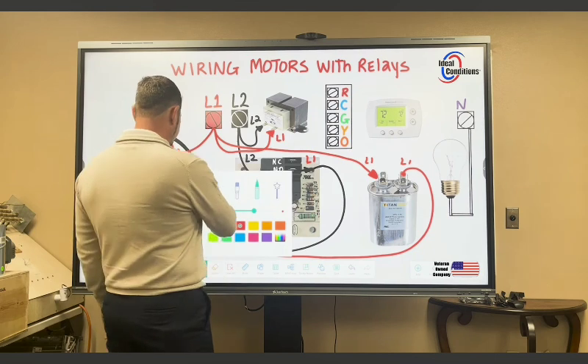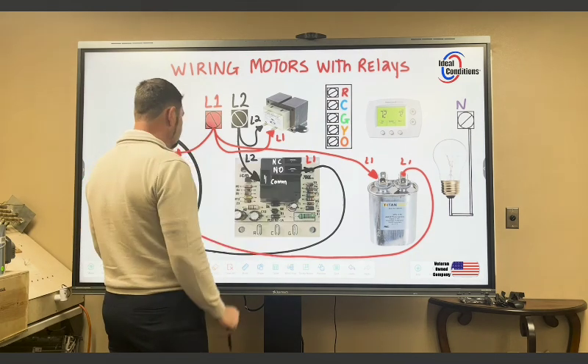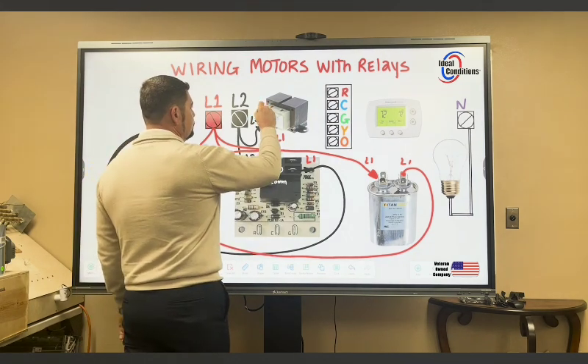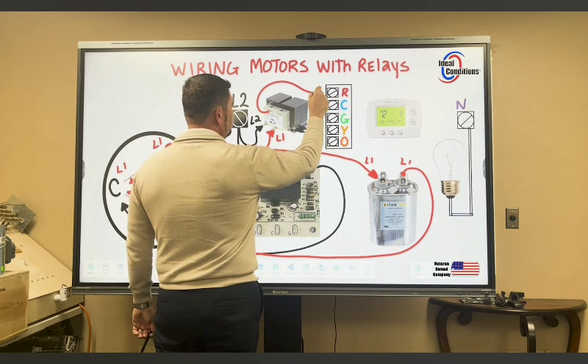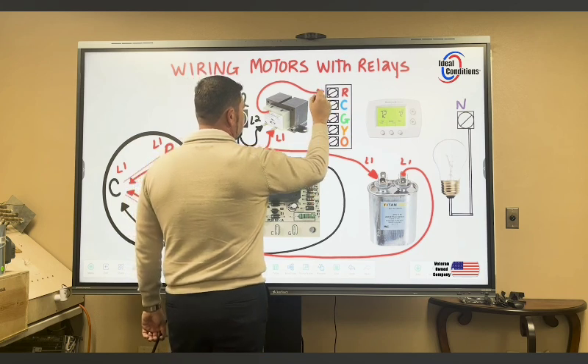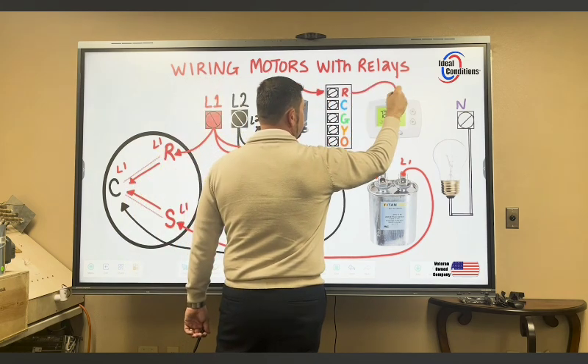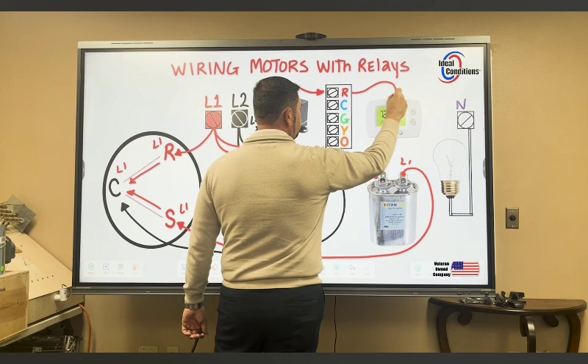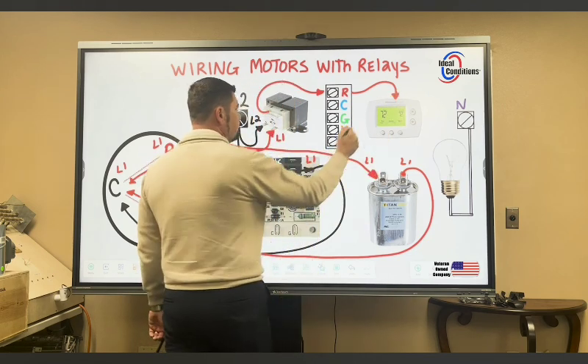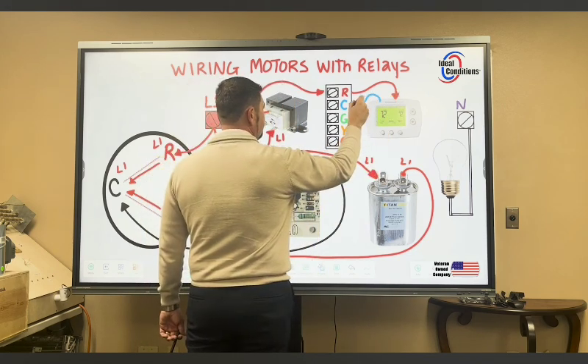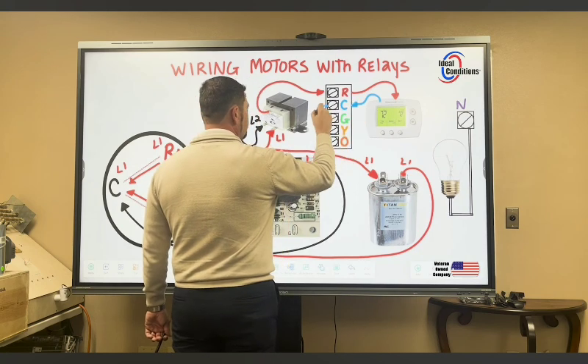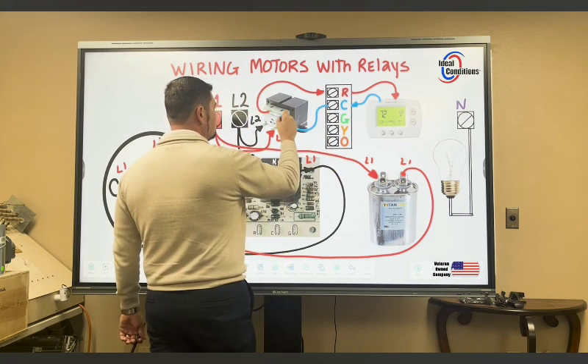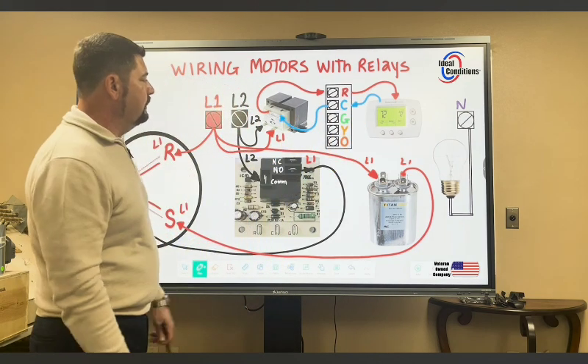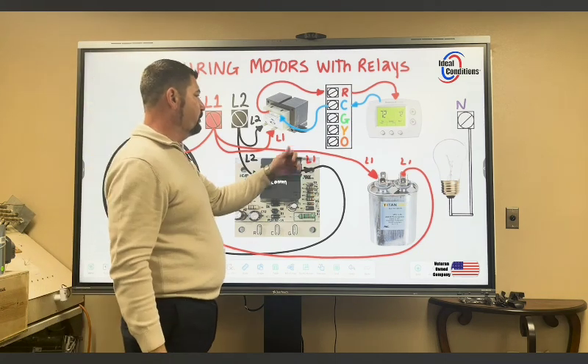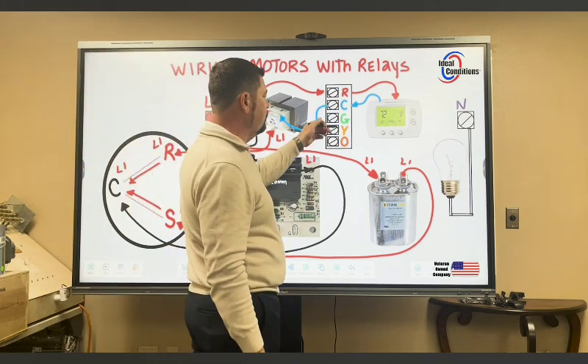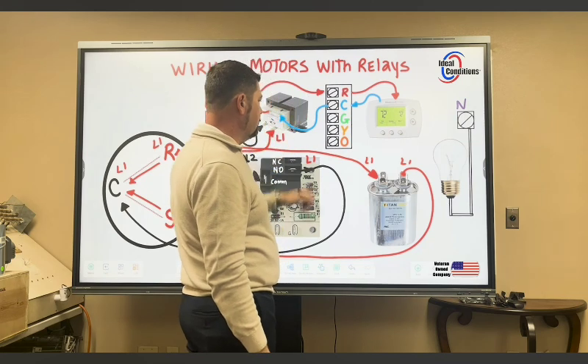Let's go ahead and get some more colors in here that we need. We're going to go ahead and take 24 volts. We're going to energize our terminal block. Coming out of our terminal block, we're going to energize the thermostat through the base plate. The face plate will energize the moment we have a path of electricity right back to the transformer. Okay. And now we can energize, and then with proper programming, we're going to get a Y call, a Y and O call, and a G call.